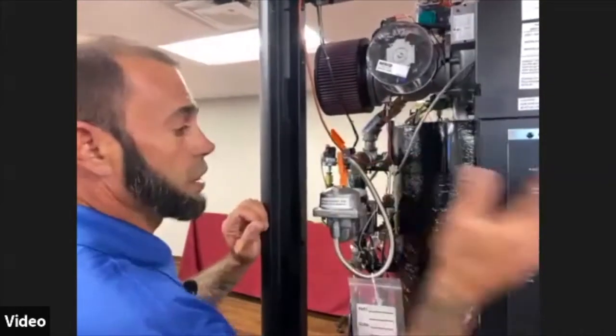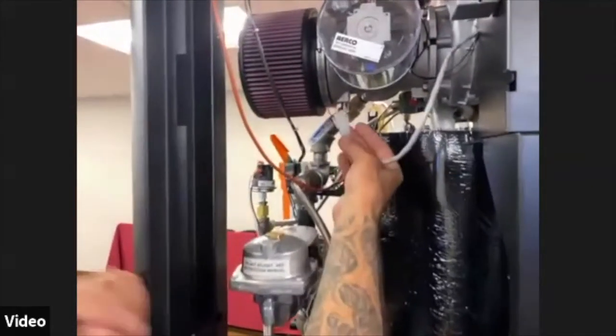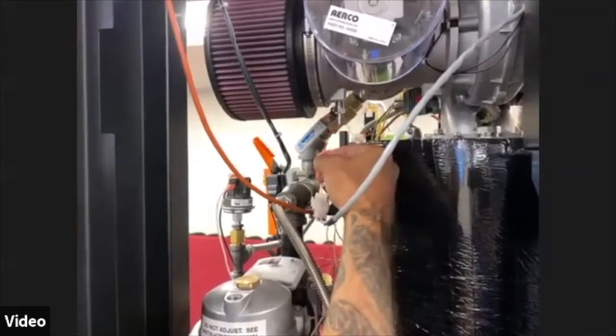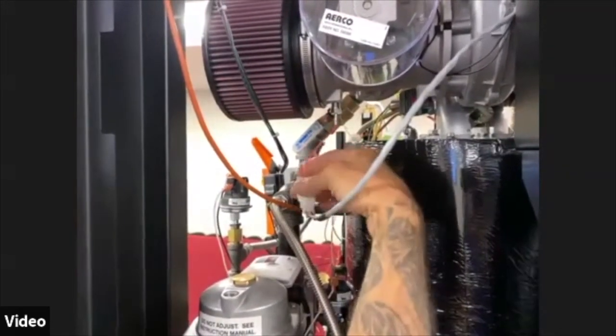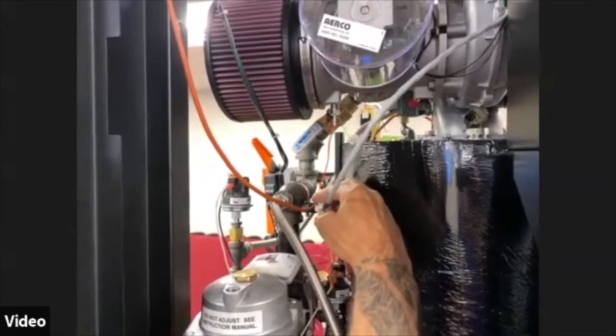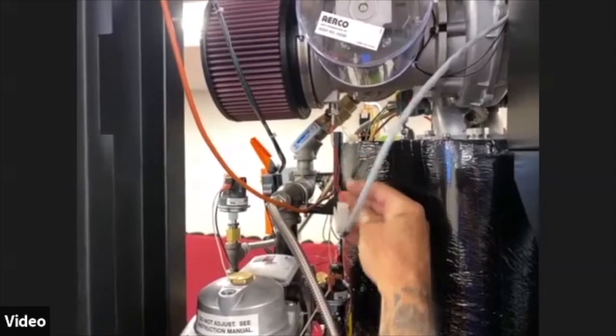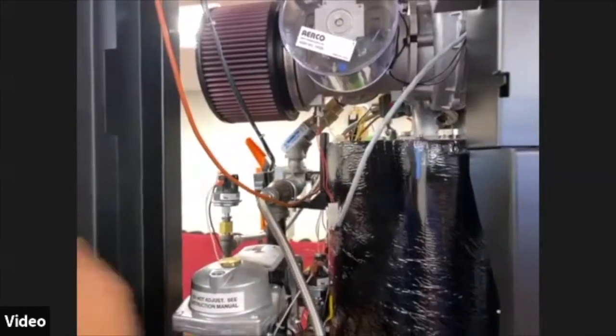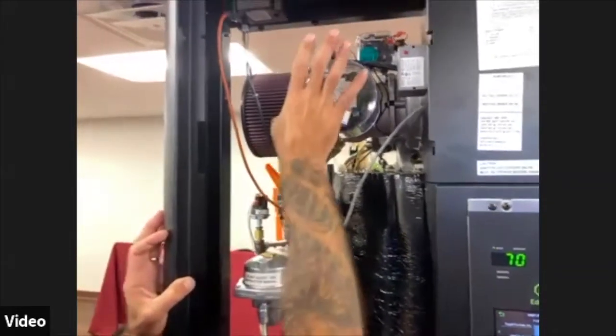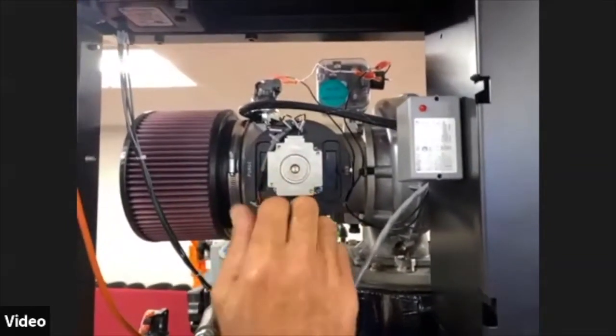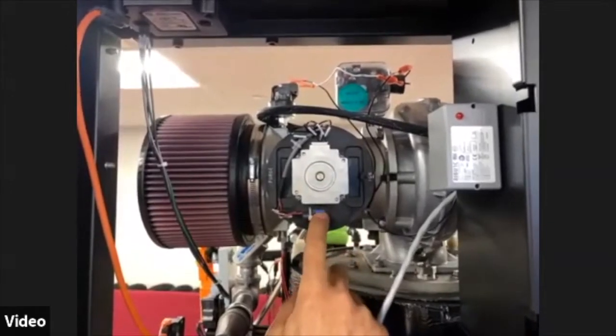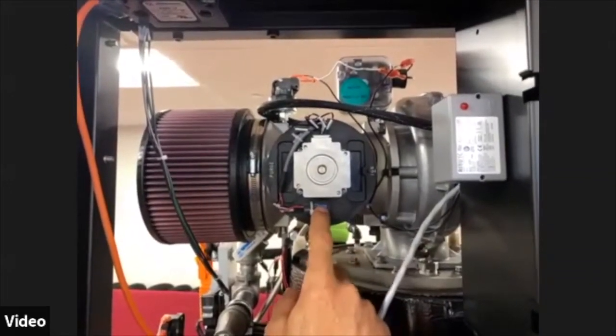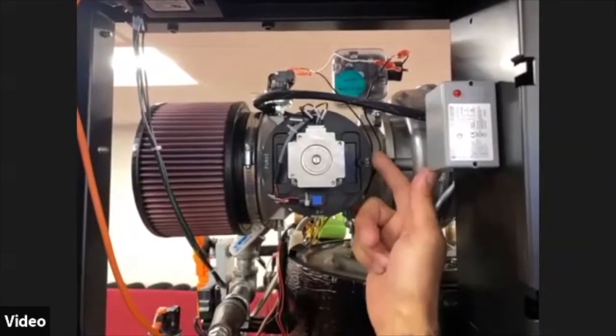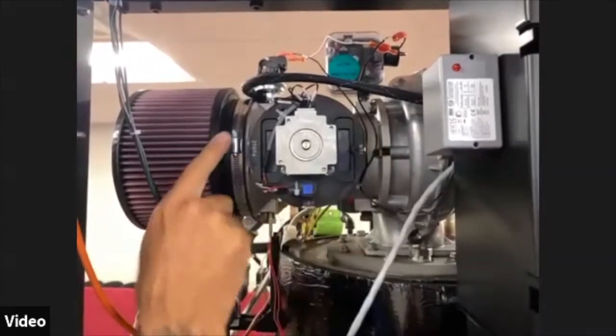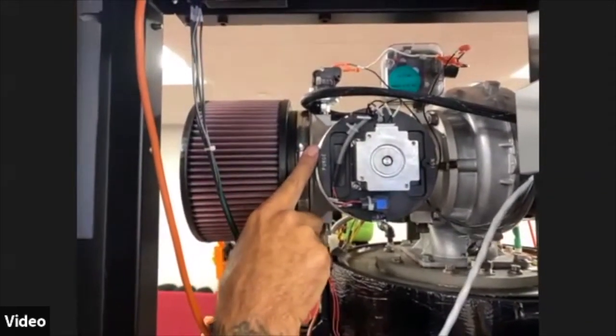We talked about that air temperature sensor on the front display. We were seeing that air temperature reading. This is our sensor right here. And one of the things I want to note about this, we're going to look at a couple sensors. This sensor is going to be the same as several of the other sensors that are located on the boiler as well. So one sensor fits multiple different locations with the same resistance. Air fuel valve cover comes off. The air fuel valve contains potentiometers, two potentiometers in here. There is an ignition switch back here. It's a 2-wire switch, proving. There's a purge switch over here, which is the same switch as well.